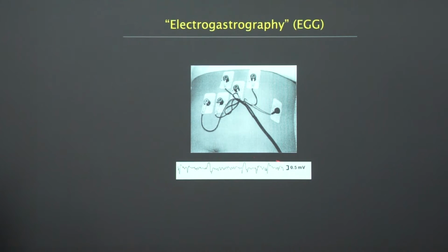One of the issues with these signals is that they're prone to noise, prone to picking up all of the electrical interference or artifact from the organs that we're not interested in when we're looking specifically at stomach activity. We pick up interference from very high amplitude cardiac signals, relative to our gastric signals, small intestine signals that are all within that same region, colonic activity, even organs like the bladder and uterus have electrical activation that we would pick up interference from, much less the external noise.